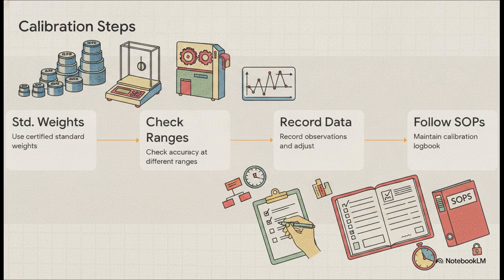It's that precise. Step 2. You check the machine's accuracy at different ranges, not just one. Step 3, you carefully record observations and tweak the instrument if it's even slightly off. And Step 4, you maintain a super meticulous calibration logbook and follow standard operating procedures, or SOPs.